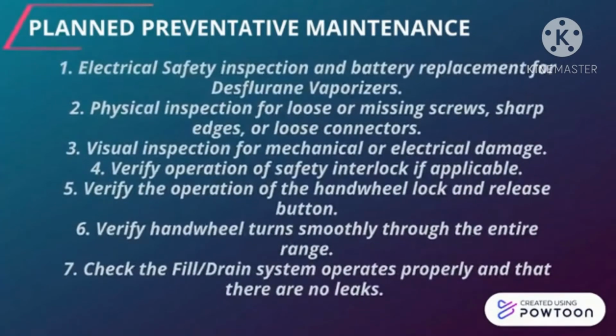Now we talk about the PPM of anesthesia machines. First, electrical safety inspection and battery replacement for Desflurane vaporizers. Second, physical inspection for loose or missing screws or loose connections. Next, visual inspection for mechanical or electrical damage.